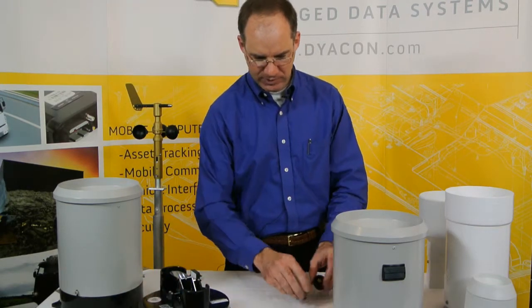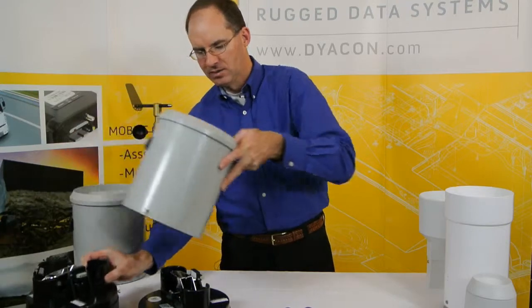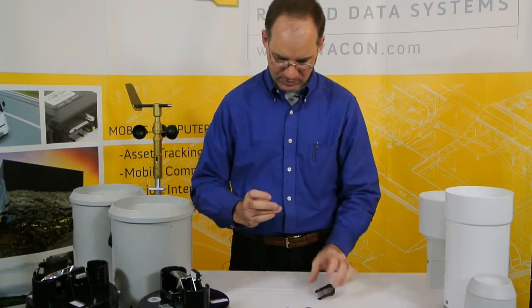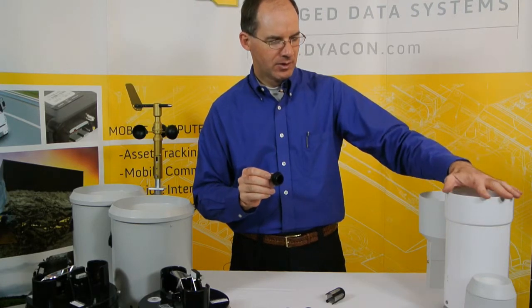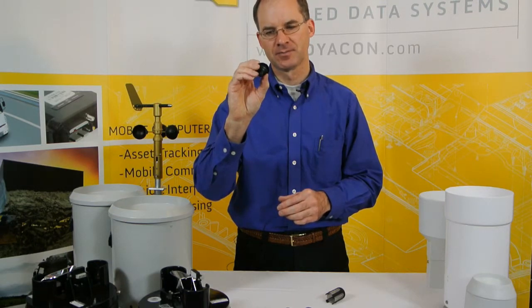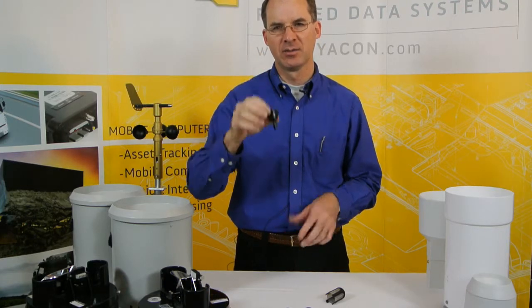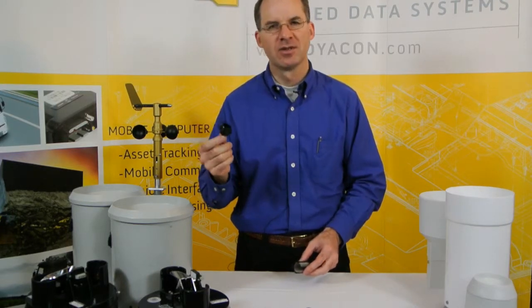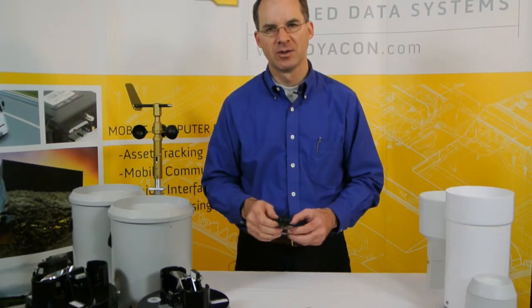The other version we carry is a standard funnel and discharge — essentially just a straight tube with a constant diameter through the length of the funnel, unlike the siphon version which has a tapered tip. This prevents dust from becoming impacted in the funnel like we had with the first gauge. The advantage of this version is that it's very accurate in areas with very minimal or medium to low precipitation rates.